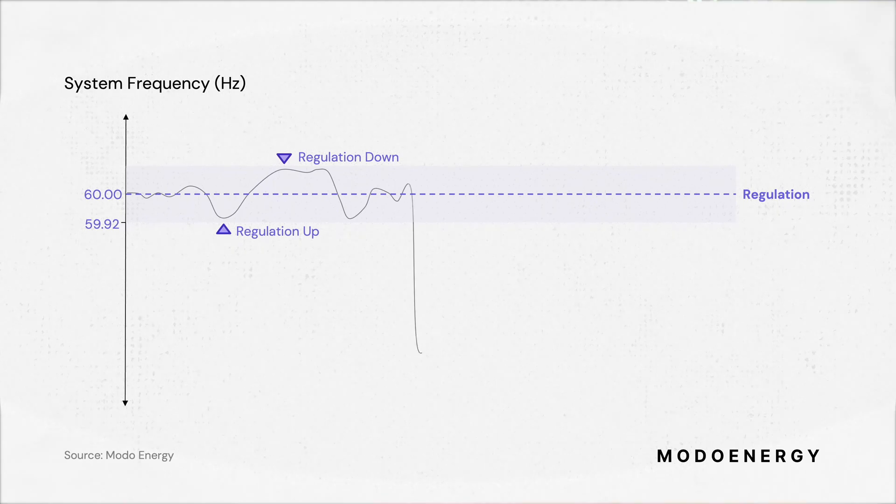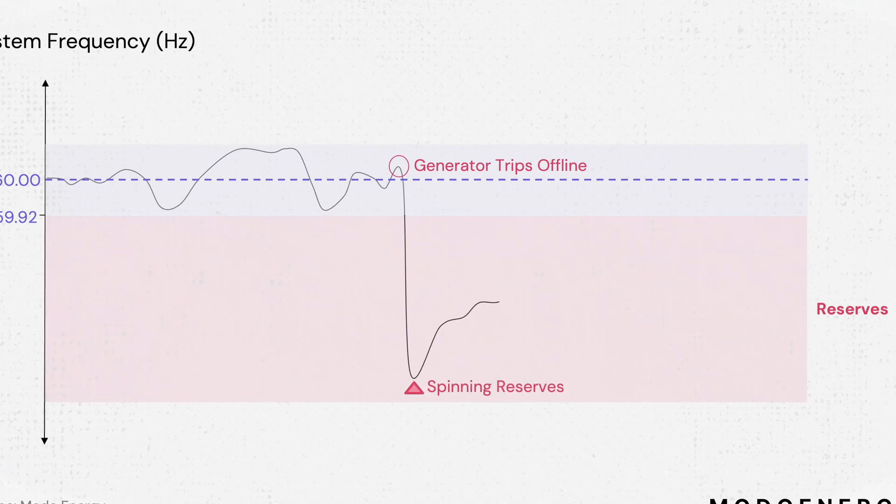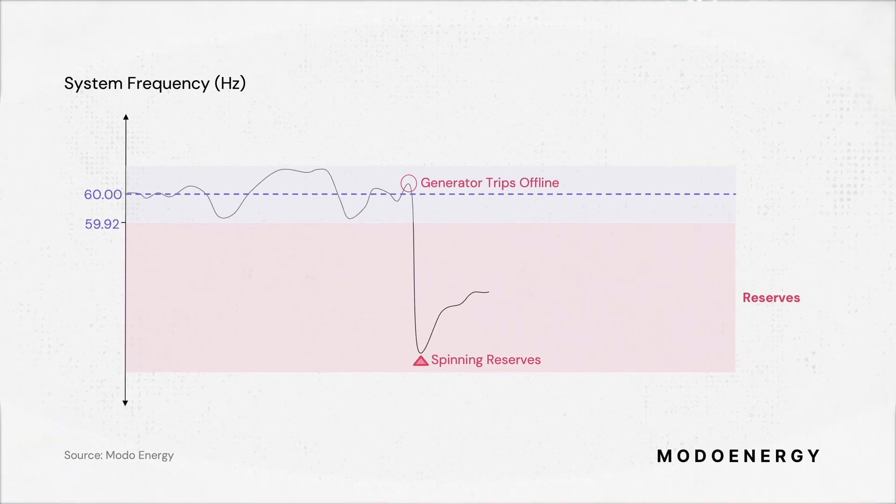Reserve services kick in during emergency conditions that significantly affect system frequency, like when a generator trips offline. The spinning reserve service kicks in first and it comes from resources that are already online or can quickly ramp up, like batteries. They turn up their output to stop frequency from falling any further.